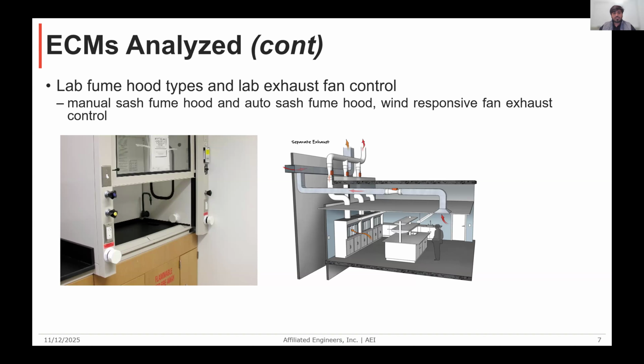But on the other hand, in auto sash fume hoods, motion sensors detect automatically when the user approaches, the sash gets opened, and it gets closed when the user walks away. So these auto sash fume hoods could provide significant fan energy savings compared to manual sash fume hoods. I evaluated both of these fume hoods. And in terms of wind responsive fan exhaust control, in this technique, anemometers are installed at the rooftop, and they measure wind speed and wind direction, and variable frequency drives, or VFDs, then adjust the speed and direction of the exhaust air that is being exhausted from the lab.